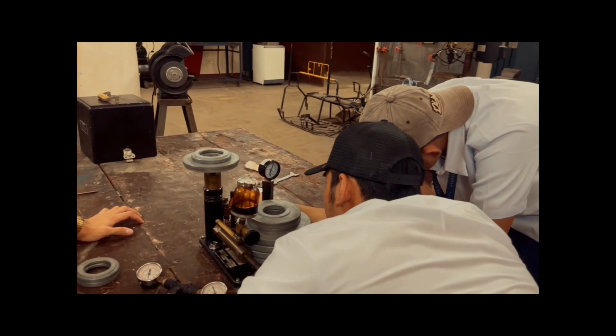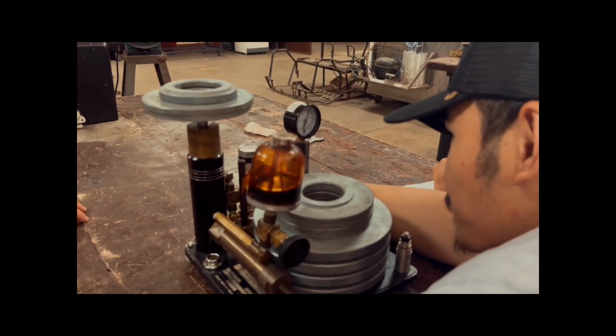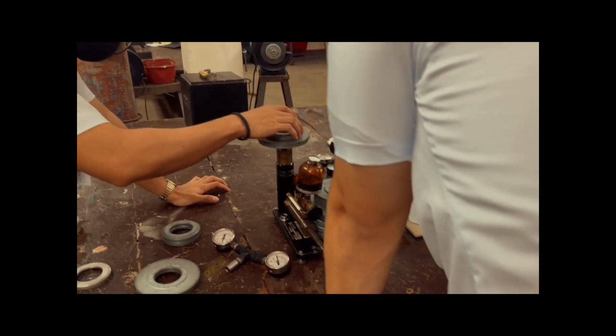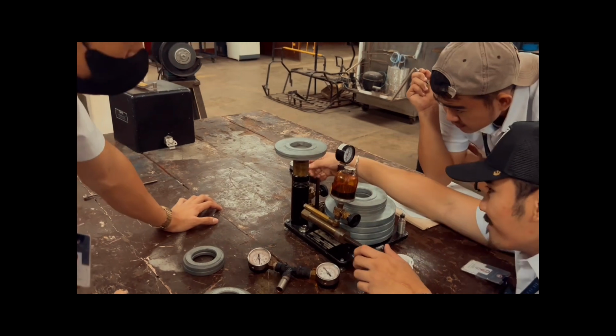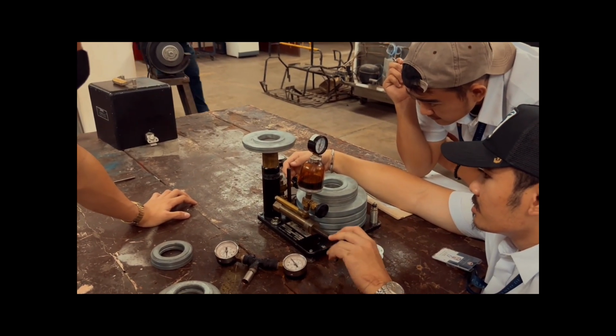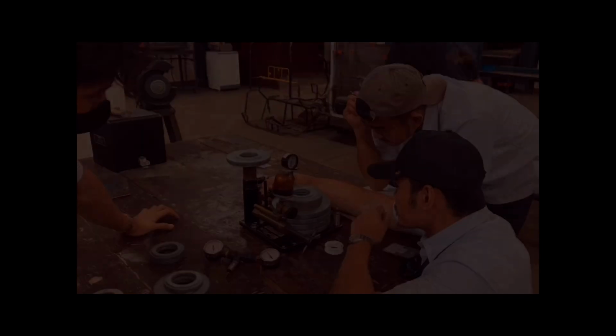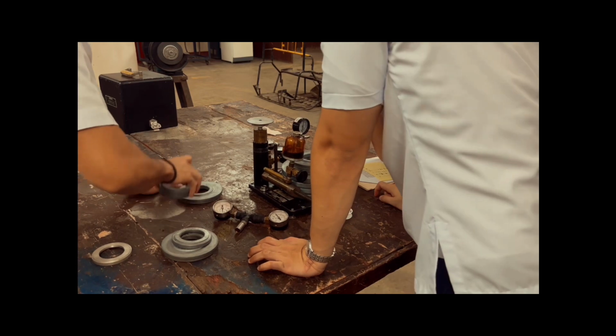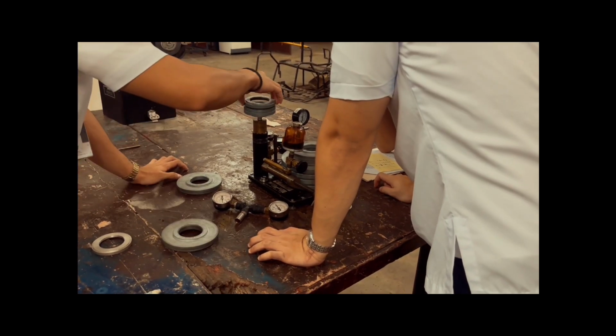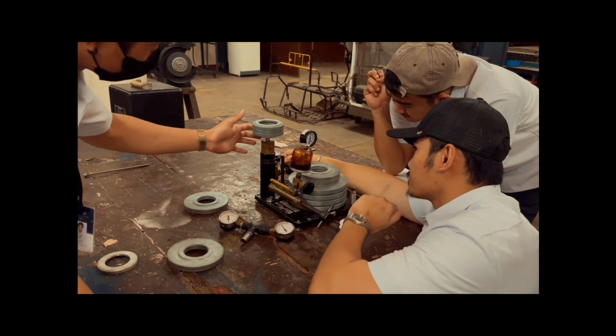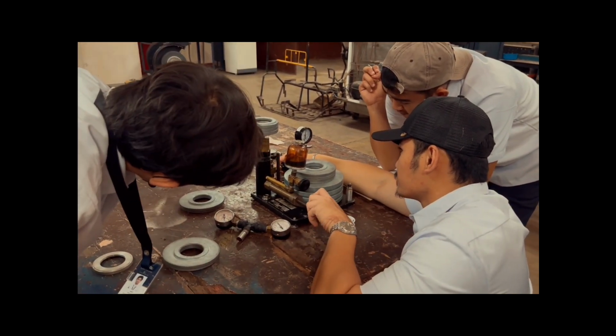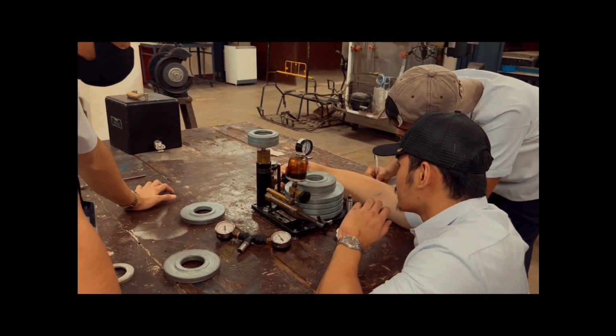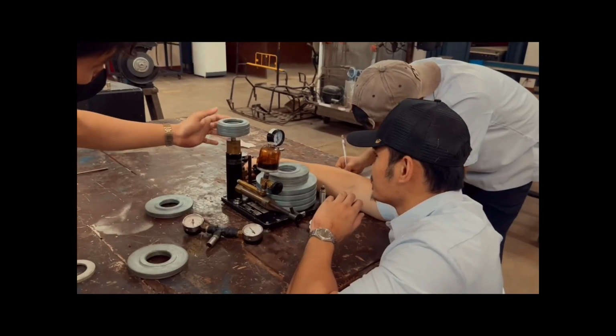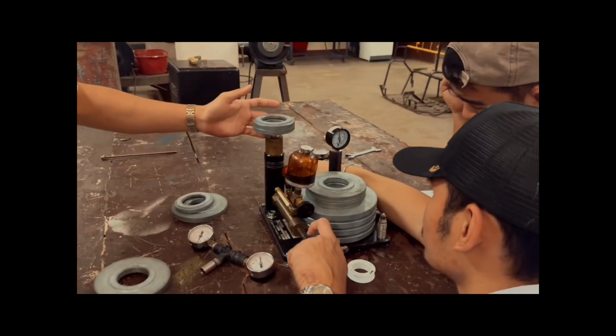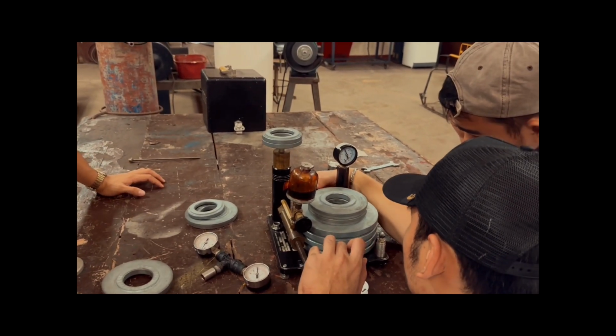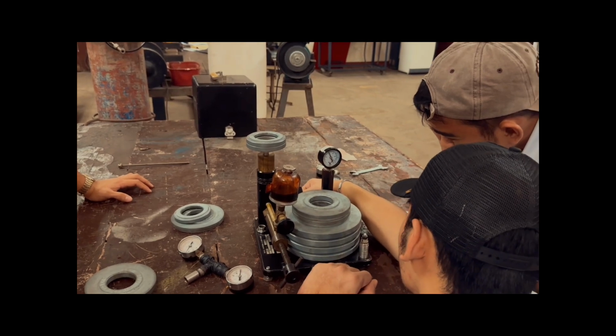In conclusion, using the Ametek dead weight tester, we successfully calibrated the pressure gauge in this experiment, ensuring accurate and reliable pressure measurements. The calibration procedure entailed applying known pressures using calibrated weights and comparing the observed pressure gauge readings. We were able to establish a calibration curve by analyzing the collected data, which provided a clear relationship between applied pressure and gauge readings. The calibration results showed the pressure gauge performance characteristics such as linearity, hysteresis, and repeatability.